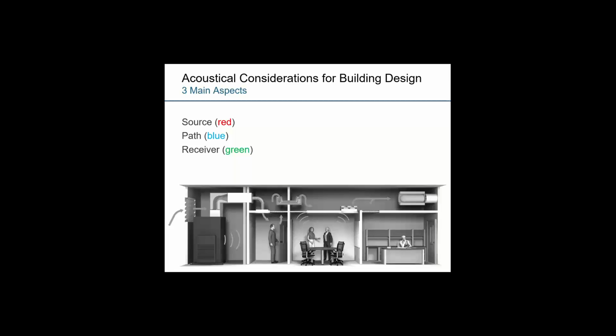Again, there's many different types of examples and things that can be potentially complicated when looking at it in this scenario. Sources can be a variety of things. They can be mechanical equipment. They can be ductwork that maybe has sound breaking out of it. They could be people or any combination of the above. The path for noise is also quite variable depending on the application and the space. Often the path for noise in a commercial building is the ductwork, the supply or return or diffusers or grills within a space, but it can be the construction of the building itself, the walls, the ceilings, the roof deck, the floor. Sound will transmit through the path of least resistance in a lot of ways.